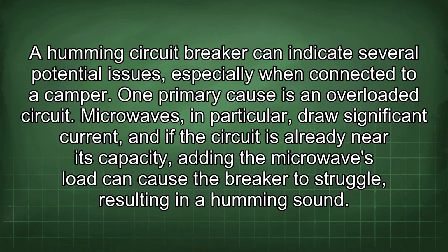A humming circuit breaker can indicate several potential issues, especially when connected to a camper. One primary cause is an overloaded circuit. Microwaves, in particular, draw significant current, and if the circuit is already near its capacity, adding the microwave's load can cause the breaker to struggle, resulting in a humming sound.